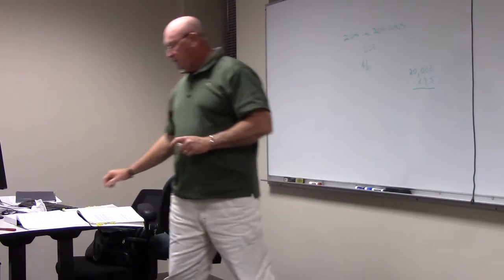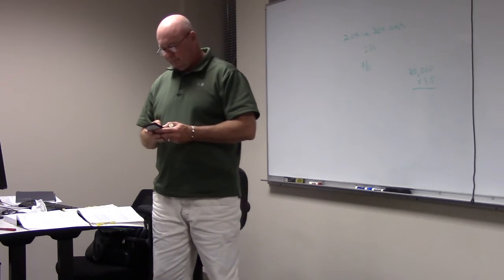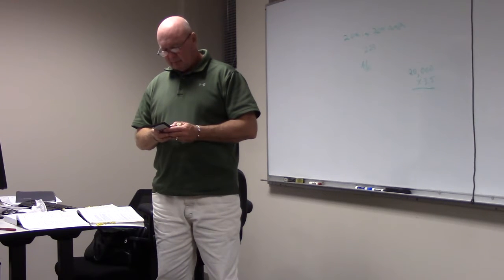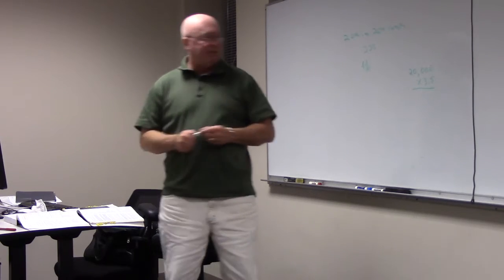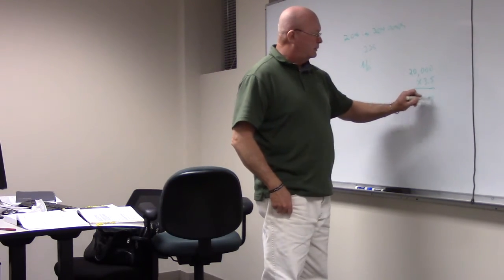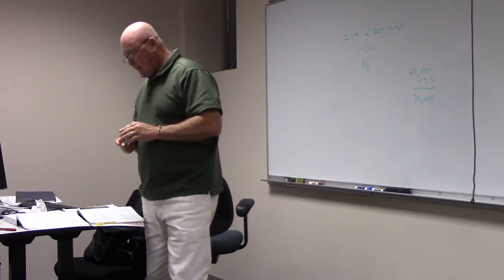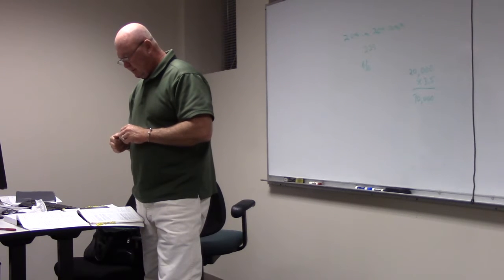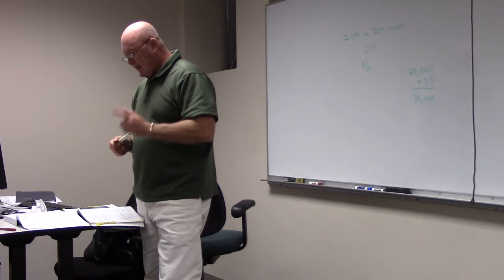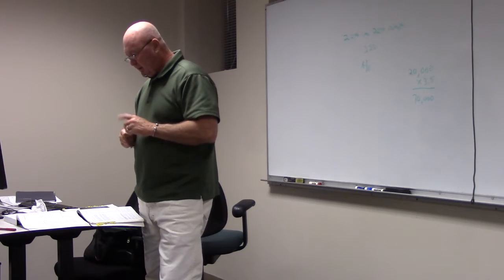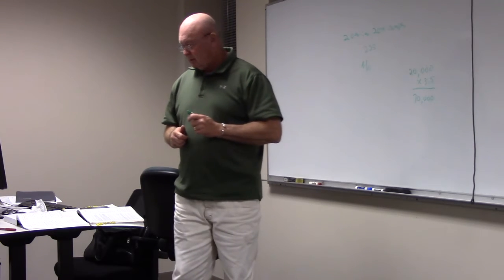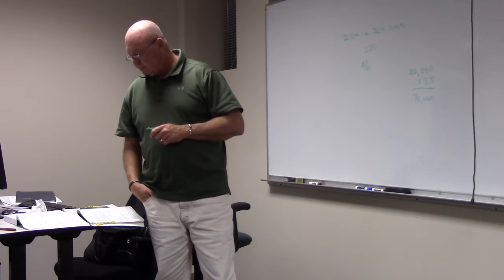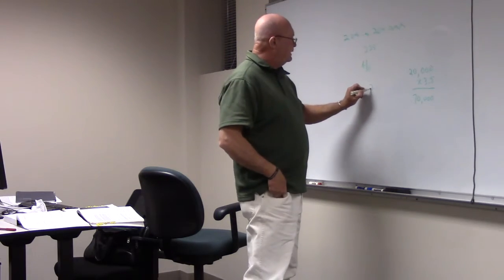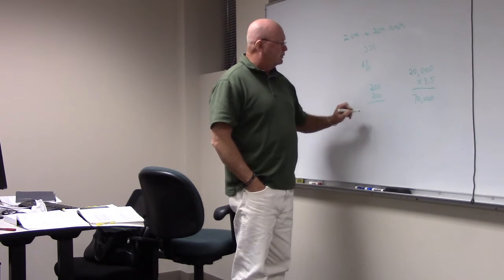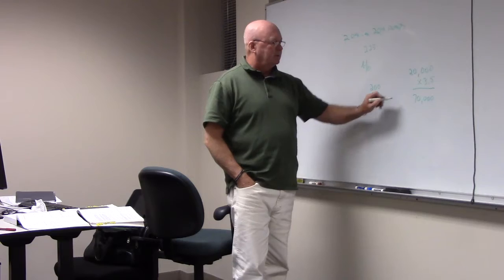So we go to 220.12, and we're going to find out an office building is how much? In 220.12, we find an office building is three and a half, times 3.5. And we multiply that out and see that it's 70,000. That's our first step, which is shown there. But that was if we used 3.5. If we look here, the actual is shown as what? It said there were 200 light fixtures at 200 VA each, wasn't it? You see that in there? It was 200 of them at 200 VA. So that's 40,000. So which one is larger? The 70.